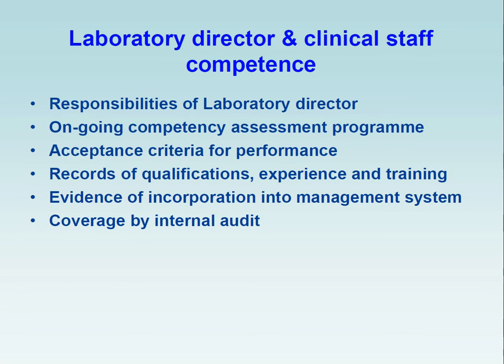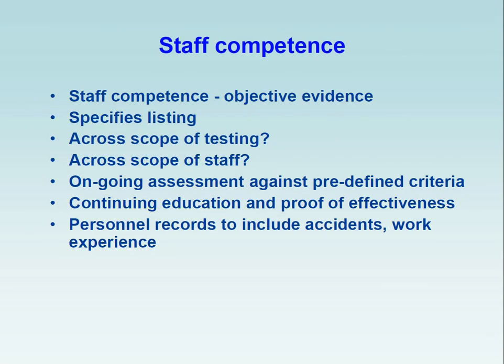Acceptance criteria for performance of all of your tests, records of qualifications, experience and training. So you now need lists of everybody that's performing tests, what their qualification is, etc. And they are responsible for making sure the internal audit is appropriate for the laboratory environment. Staff competence, objective evidence. So not say, oh, well, I think they belong to that scheme. They actually need the pieces of paper. I did this scheme, this was the result, this is my reflection on it. And it does specify that you need lists.